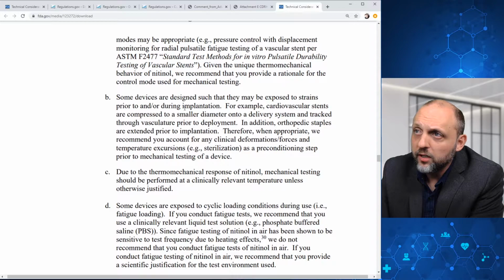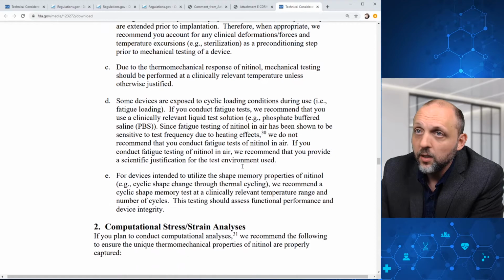Some devices are designed such that they may be exposed to strains prior to and/or during implantation. Therefore, when appropriate, FDA recommends you account for any clinical deformations or forces and temperature excursions as a preconditioning step prior to mechanical testing of the device. And due to the thermomechanical response of nitinol, mechanical testing should be performed at a clinically relevant temperature.